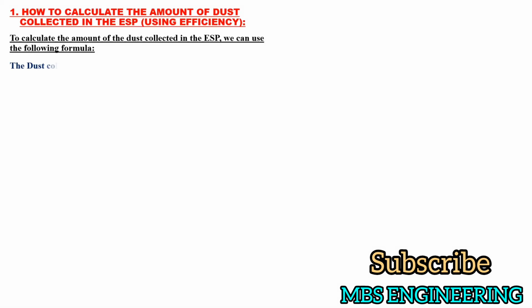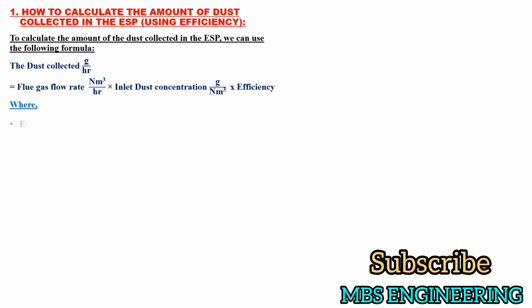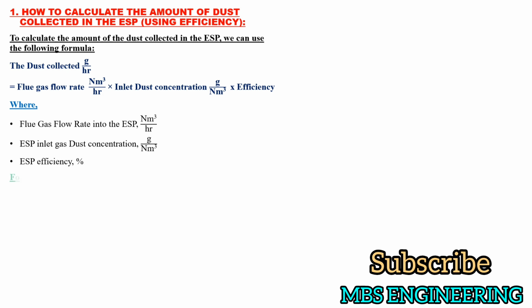The dust collected in gram per hour is equal to the flue gas flow rate, Newton meter cube per hour, multiplied by the inlet dust concentration, gram per Newton meter cube, multiplied by the ESP efficiency. Where the flue gas flow rate into the ESP is in Newton meter cube per hour, the ESP inlet gas dust concentration is in gram per Newton meter cube, and the ESP efficiency is in percentage.